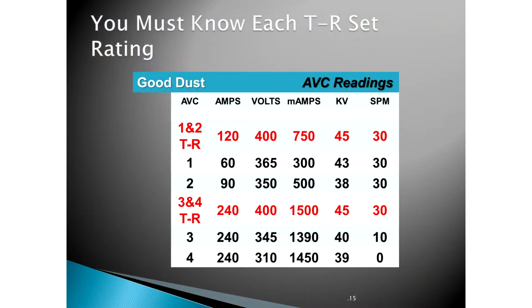The second field, is it doing its job? Yes, it's controlling sparking. The third field, it's a bigger transformer. Is it doing its job? Well, it's set to run at 30 sparks per minute and it's only running at 10. Is it doing its job? Why do you say yes?